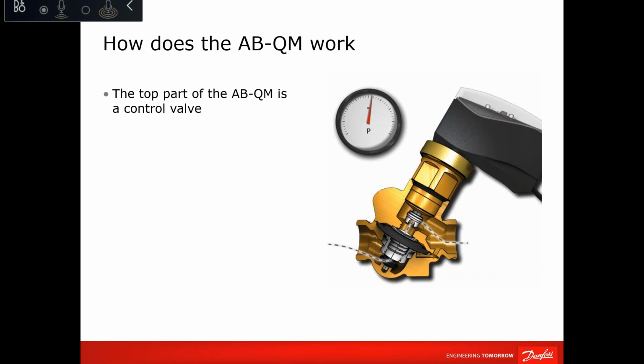Do we have to do any periodic maintenance for the PICV and the actuator? No. Simply, no. The valve is maintenance free. There is no requirement for any maintenance to the valve or the actuator. You don't have to clean, you don't have to check, you don't have to do anything.